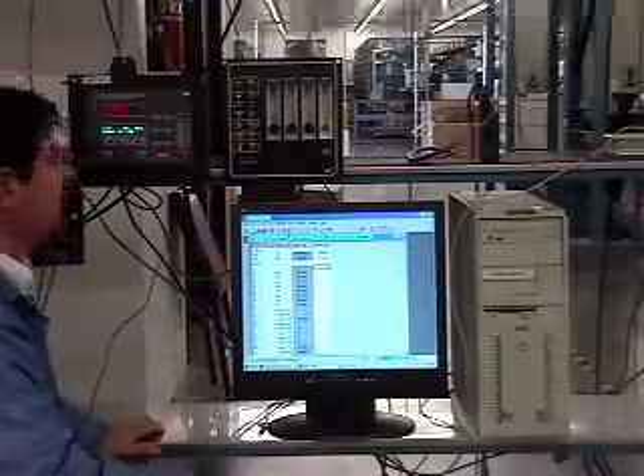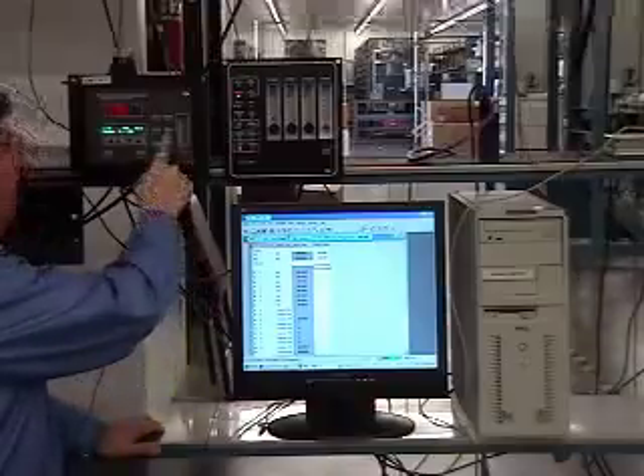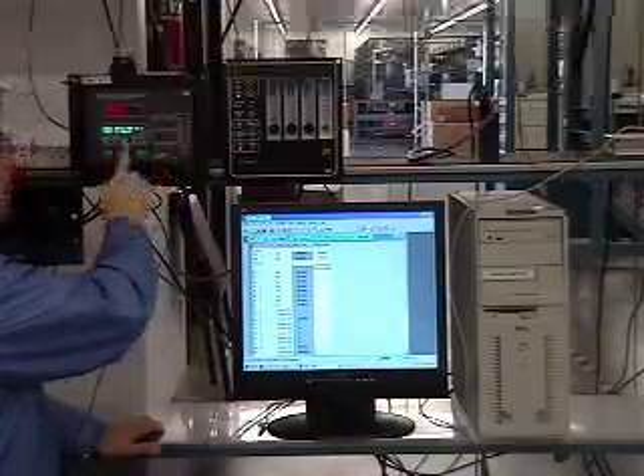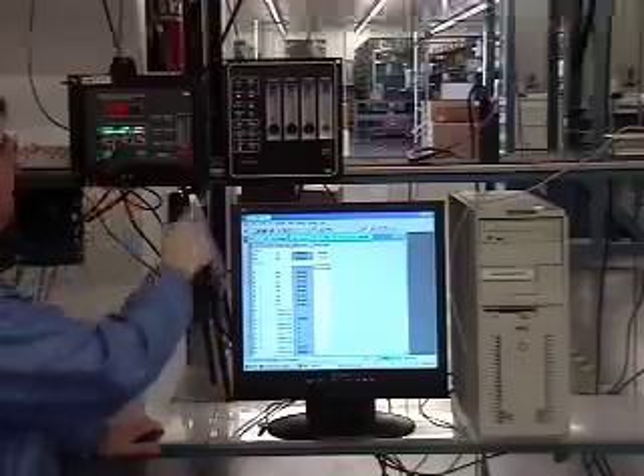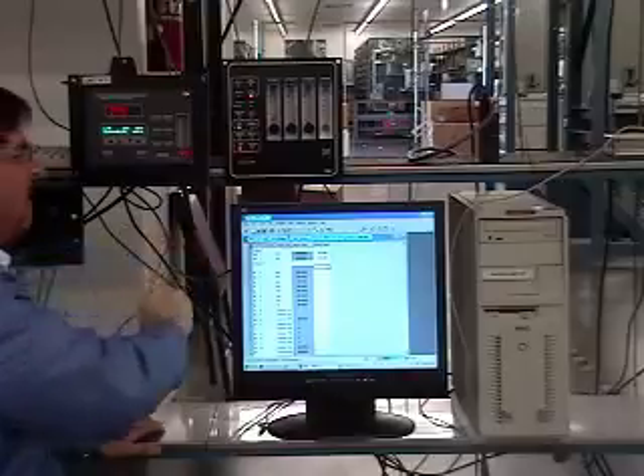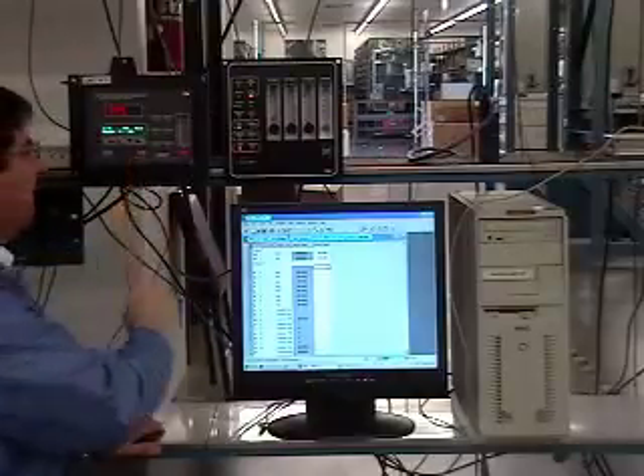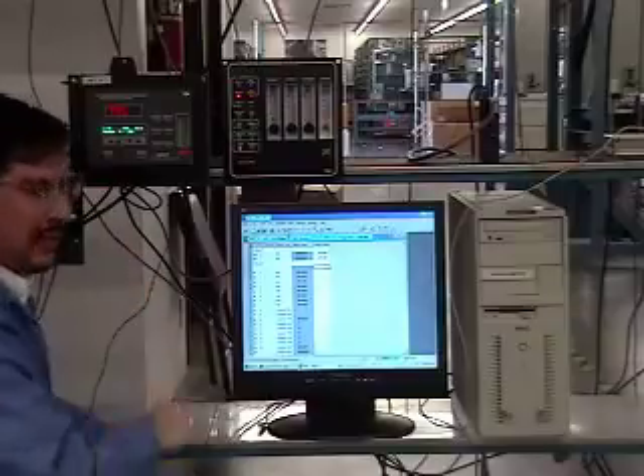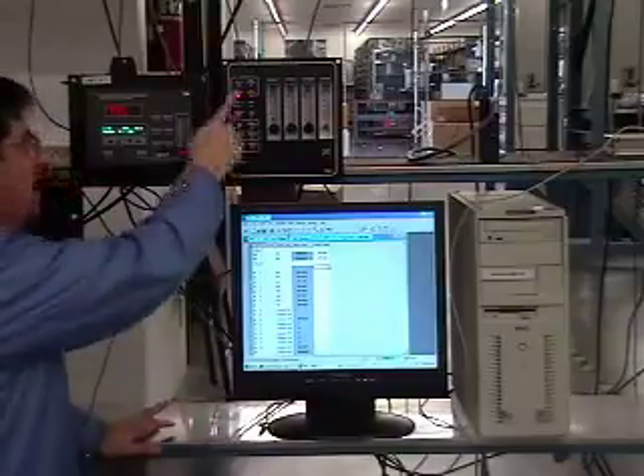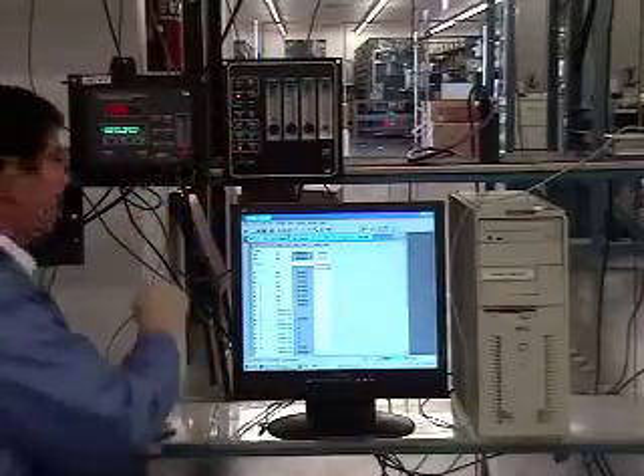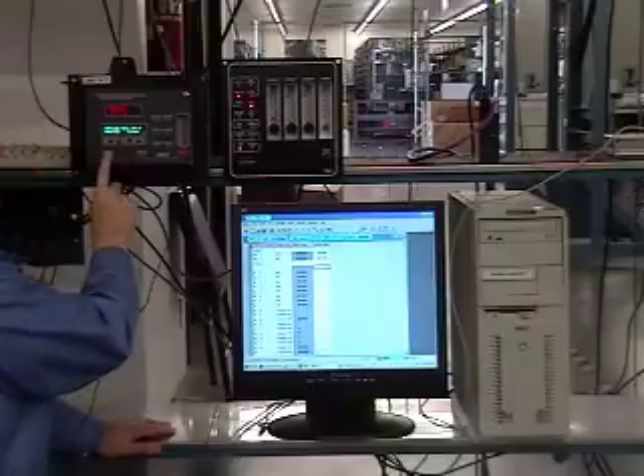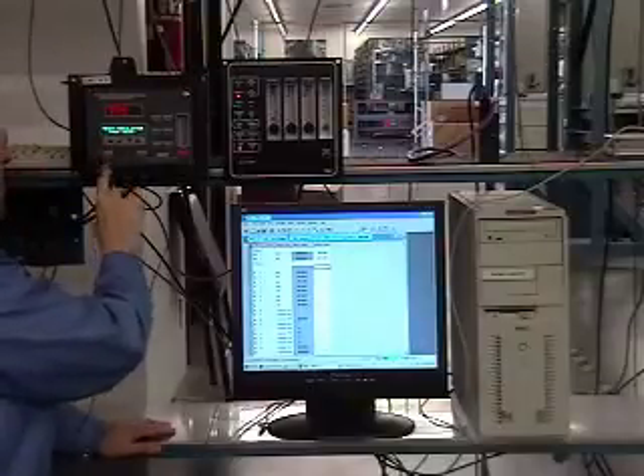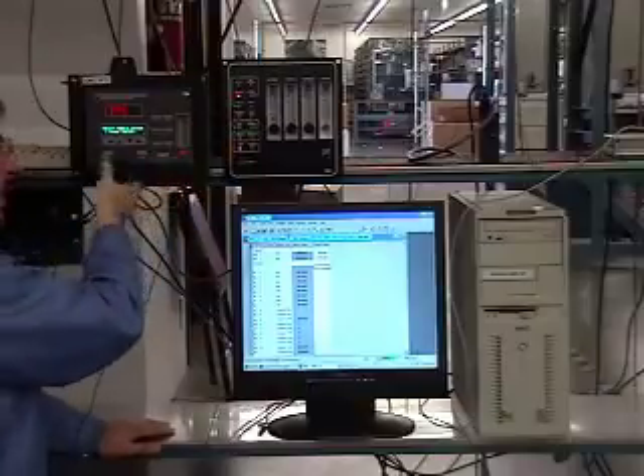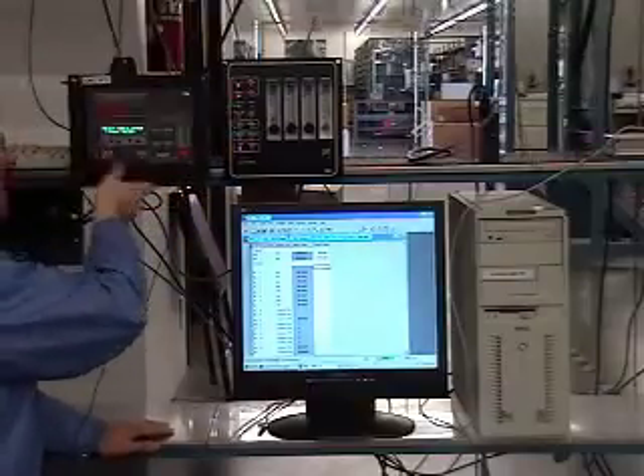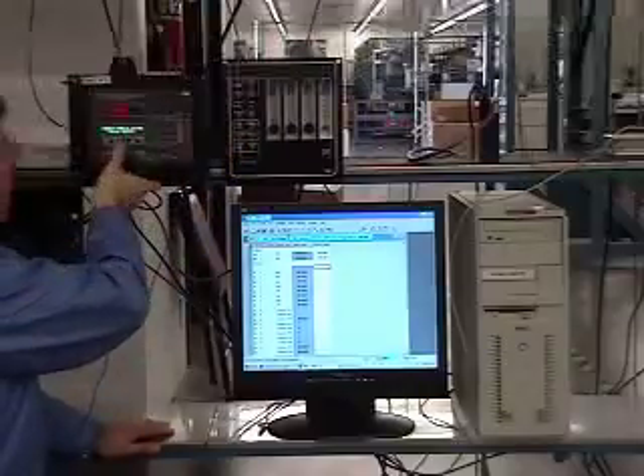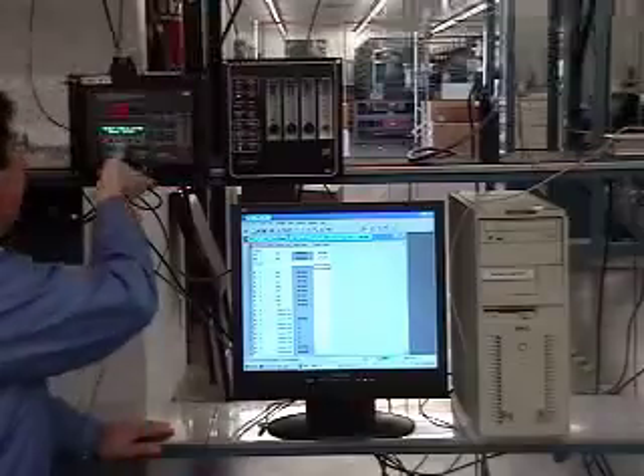Okay, so this is a little bit different. And now I'm going to go ahead and go to zero mode. Immediately it changes to the low calibration gas mode. I'm escaping now. But that's not all I can do, because this unit has special software so that I can exploit that I have 3 sample gases. So within the system menu, I have a function called stream. And I can select different valves over here, 1, 2, and 3. Right now it's selecting 1. I press enter. It will change it to 1. Select 2. Select 3.